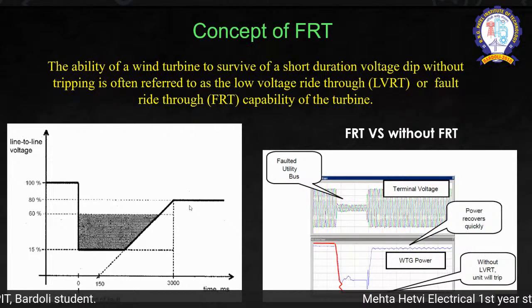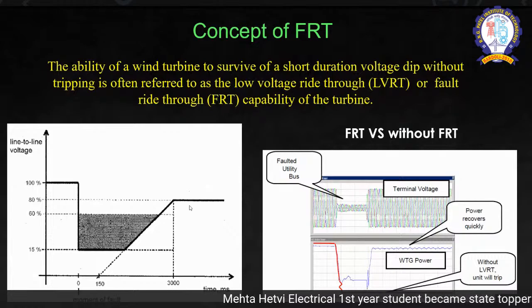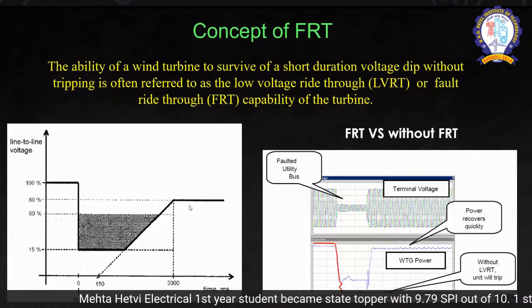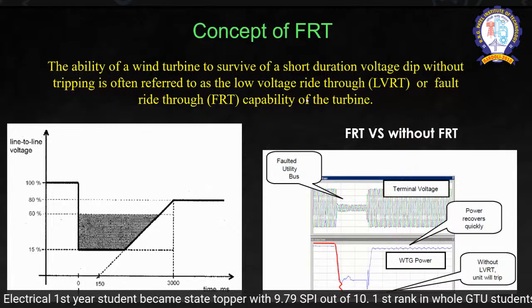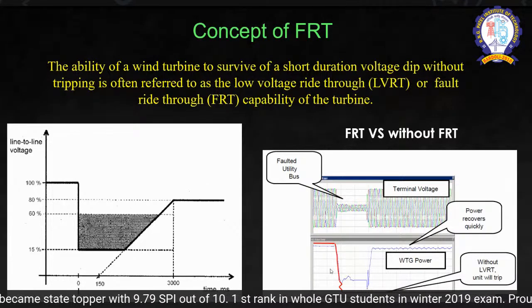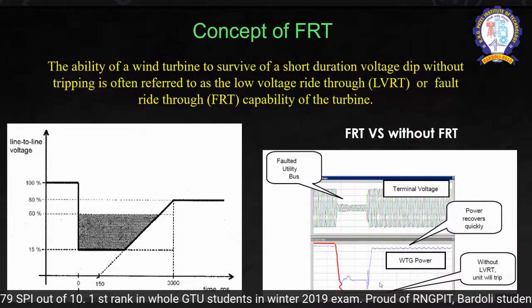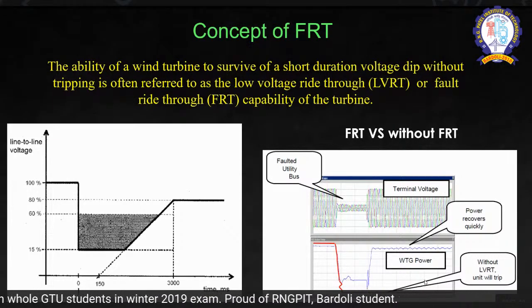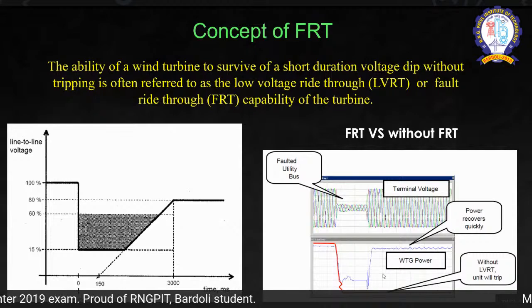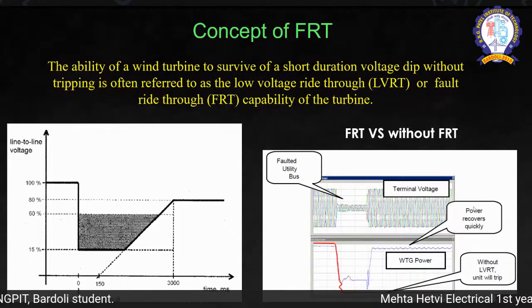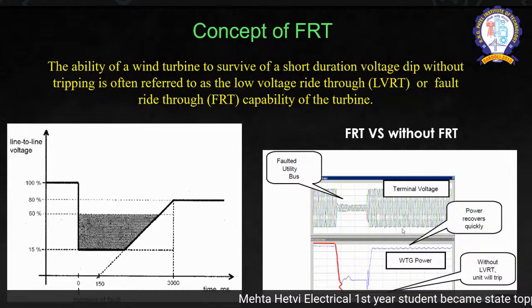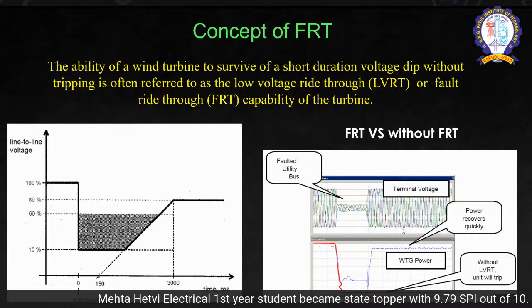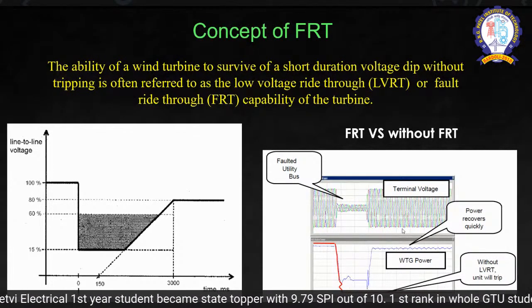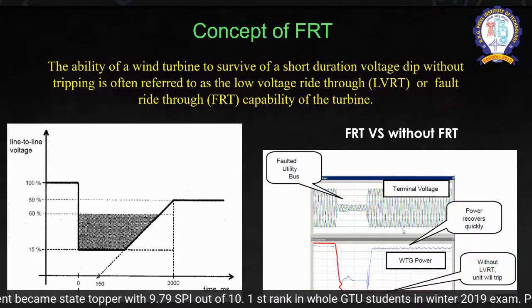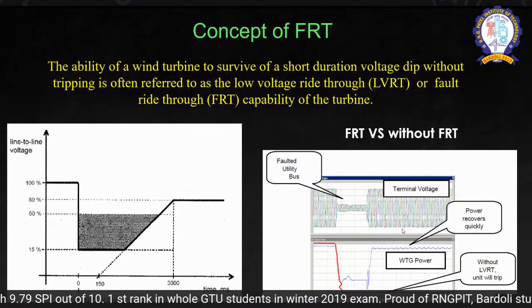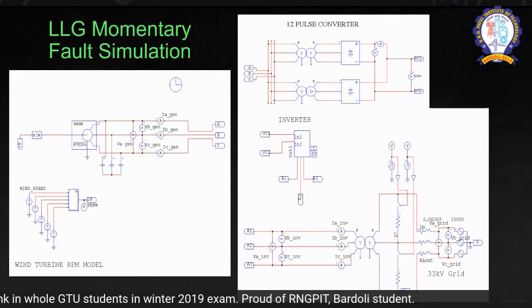This feature of the turbine generating system is known as FRT or low voltage ride through, LVRT. This is the common example of the comparison. Without the LVRT option, it might be a trip, and with the LVRT option, it might survive and the power will recover quickly. With the incorporation of FACTS devices, they will provide some power in this duration. So the wind turbine is tightly connected with the utility or grid.